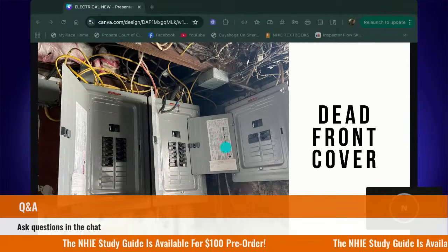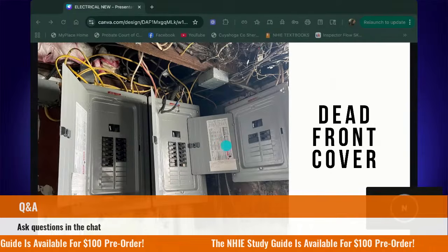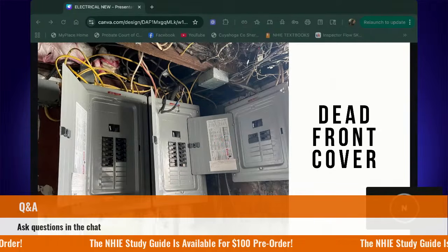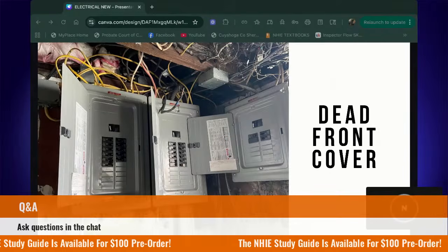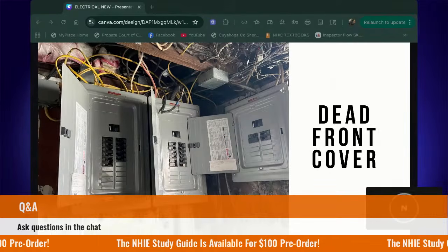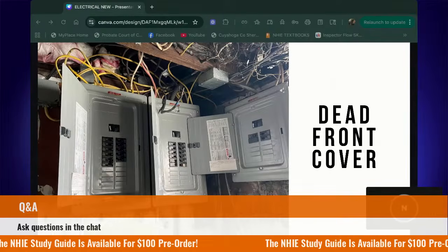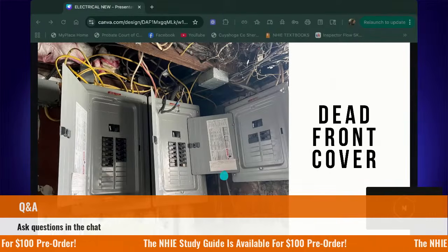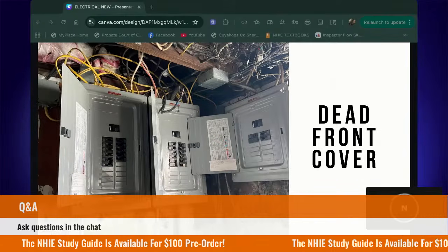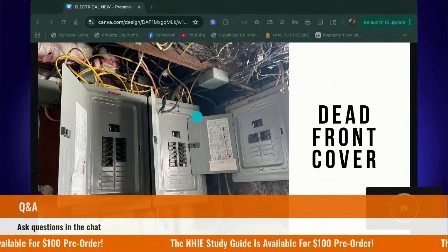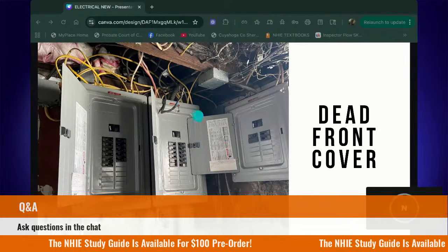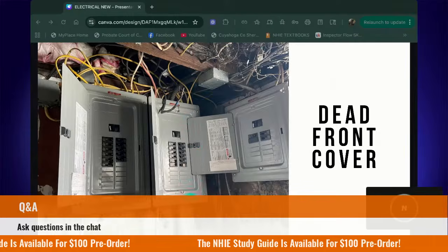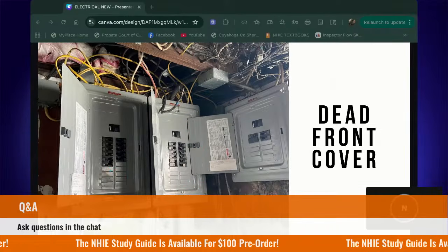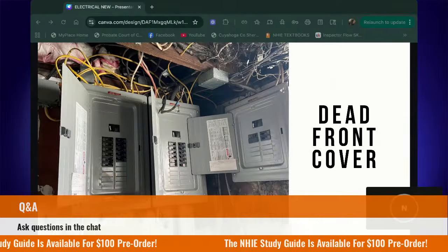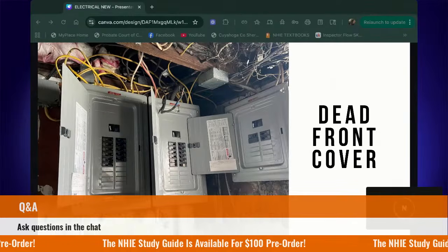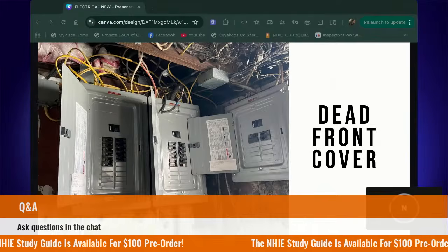So the openings in the dead front are for the breaker handles. So these openings here, this is where your breaker handles go, and they are sized basically to limit access. They don't want you to access the live part of it, just the actual handle. The dead front is typically secured, depending upon the type of panel, by screws. Typically there are six, two at the top, here, here, and here. And so you have to remove those six screws. So again, this is where paying attention could literally be the difference between you getting fried, dyed, and laid to the side and not.